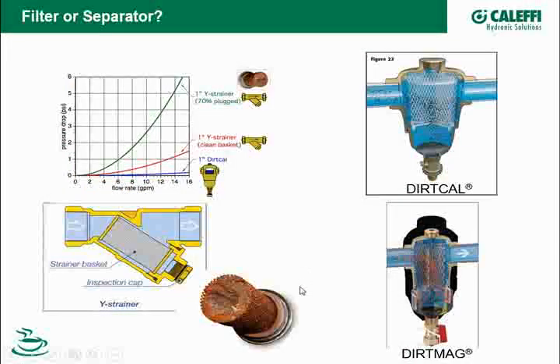Filters or Y strainers, I'm of the opinion every system out there should have some sort of filter device on it. For years we've used the Y strainer. Be aware that a Y strainer, sometimes called a cartridge type of filter, has limitations in the coarseness of the mesh as far as what it's going to filter out. But the other thing with the Y strainer, if from day one, here's a brand new 1-inch Y strainer put in the system, it's got a little bit of pressure drop going through it because, again, all the fluid's got to go across that screen as it flows through there.